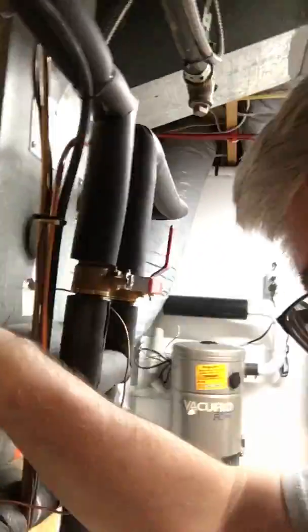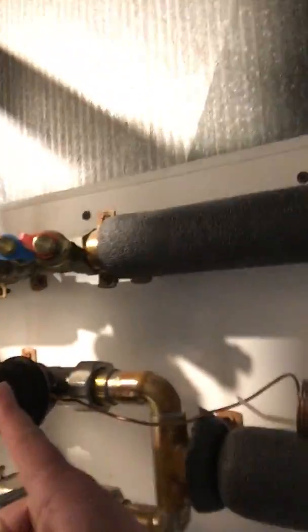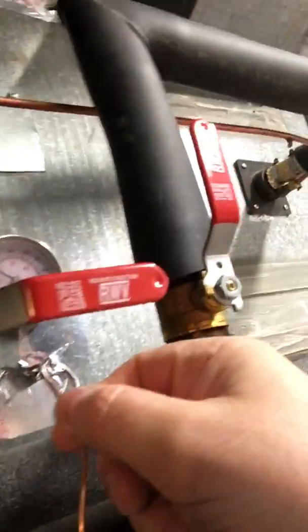So let me show you what's going on here. This is the return line going back. This line right here is the return. That's a return going back. But we also have two control valves, and I want to point out what they are. This is a thermostatic control valve, which means there's no power to it. That controller is connected to this capillary tube right here, which goes into the ductwork. That device maintains constant air temperature into that space. Again, we're using radiant for heating, so we don't need to use it as a primary source of heat.